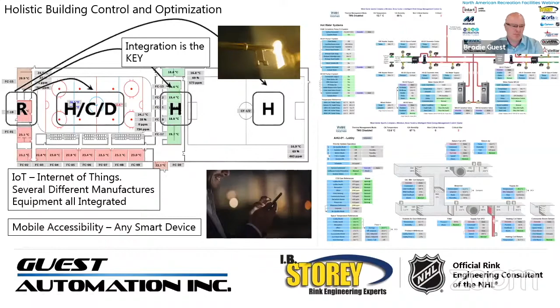So how does this facility achieve such a low energy footprint per square foot? Expertly engineered sequences and an industry-leading thermal management system. This TMS is highly complex, yet completely automated and simple to the end user. The thermal management system is always monitoring, calculating, and re-ranking every 10 minutes of operation or every time the ice plant starts up. The TMS is so intelligent, it knows how much heat is available from either the plant or from the backup water heaters, and how much heat is required within the facility. Then it will choose where to direct that energy.